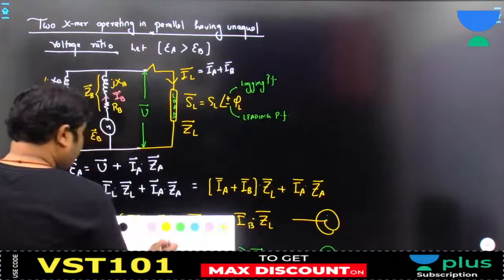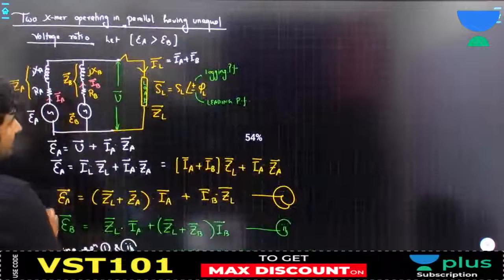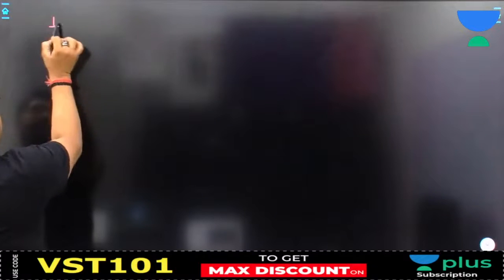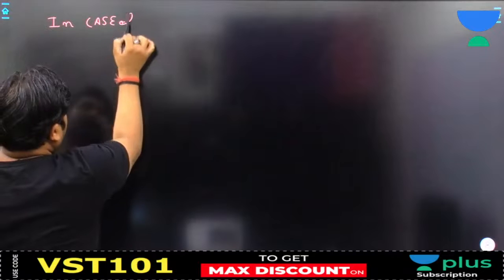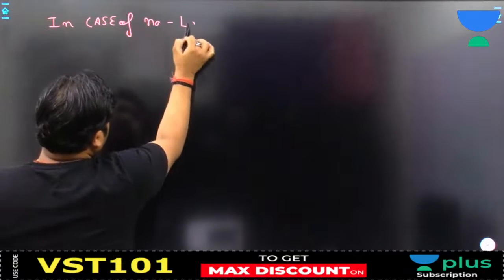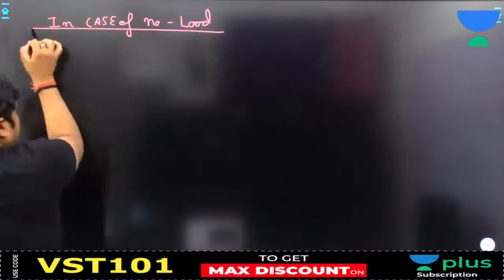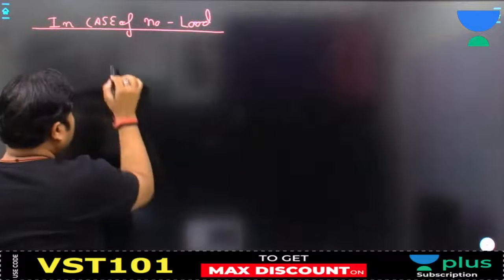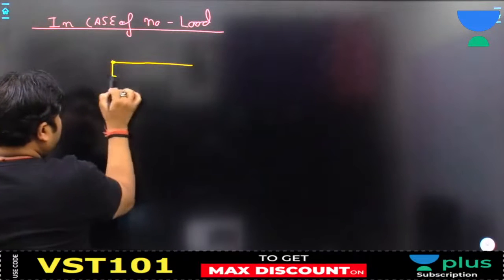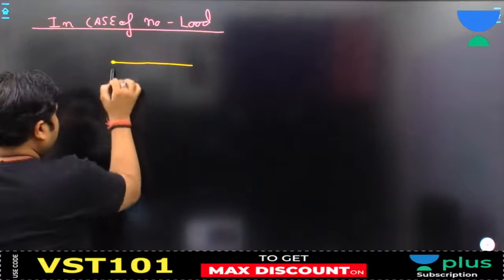So automatically the turn ratio, or voltage ratios, will vary slightly, and because of this there will be circulating current within the transformer. Now let's talk about the circulating current. Please see, what is the circulating current? In case of unequal voltage ratio transformers at no load, let's examine this.